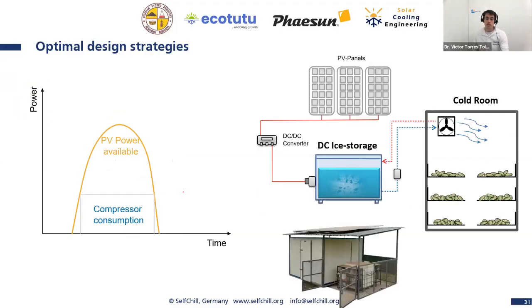What happens if we have no batteries at all? Let's think about direct drive heat pumps, compressors that can run on direct drive. We don't have batteries. Now we have an ice storage, a thermal storage. You can see it here. Then from the thermal storage, we will run the cold water inside the cold room to generate cold air. This is clear. Okay, this sounds very nice at the beginning, right? You don't have an inverter, you don't have a charge controller, you don't have batteries at all. So it sounds very good, but it has a disadvantage.